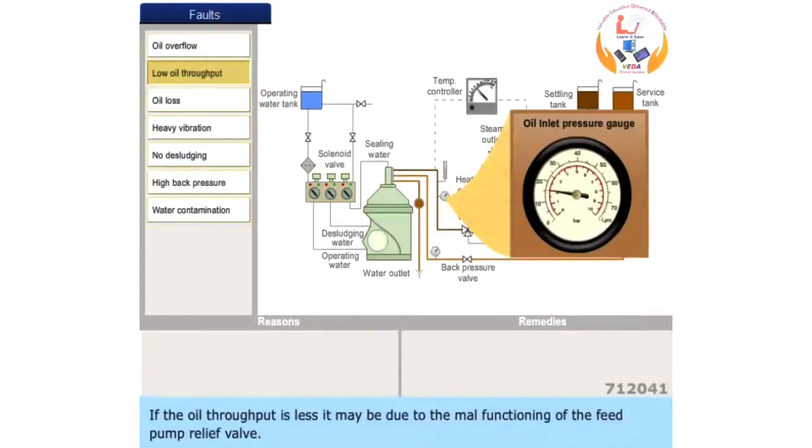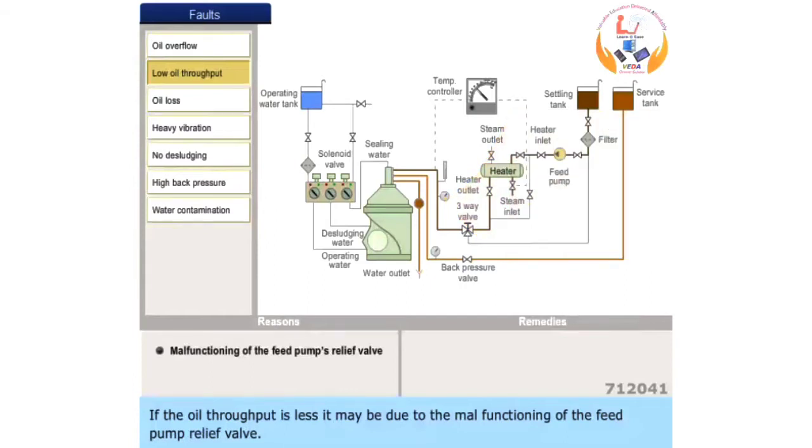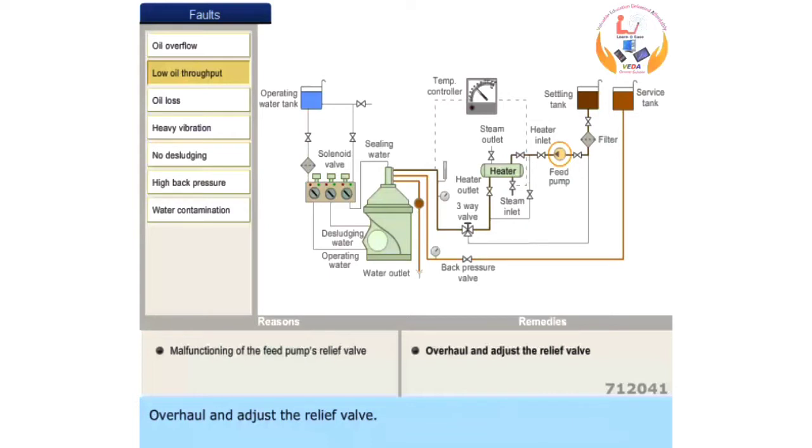If the oil throughput is less, it may be due to the malfunctioning of the feed pump's relief valve. Overhaul and adjust the relief valve.